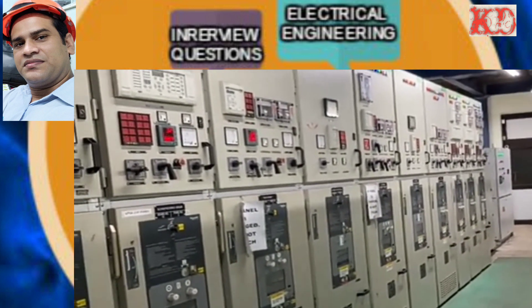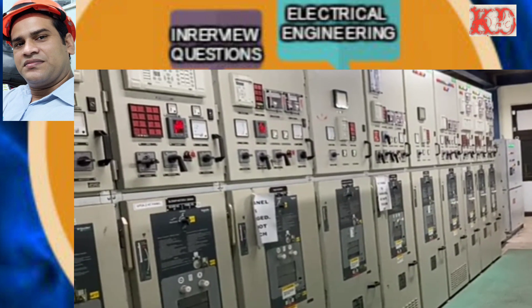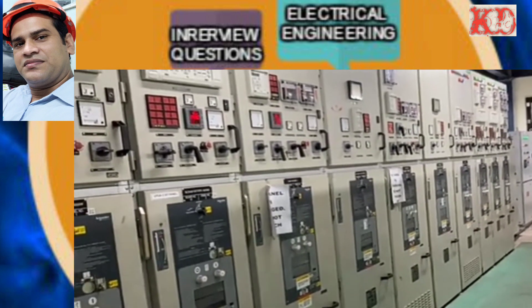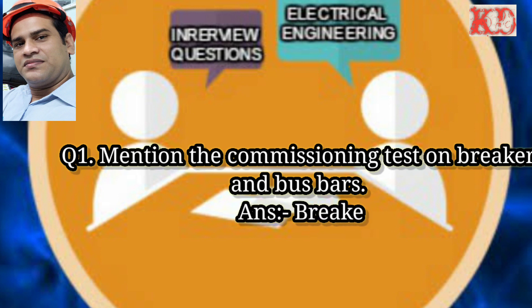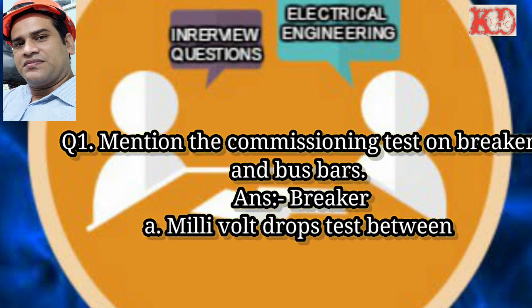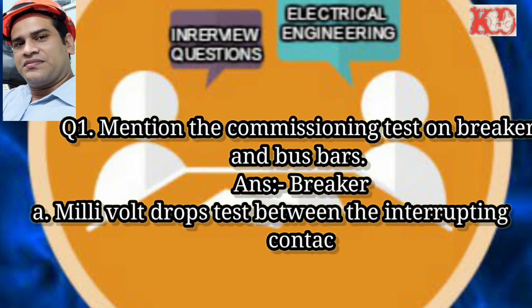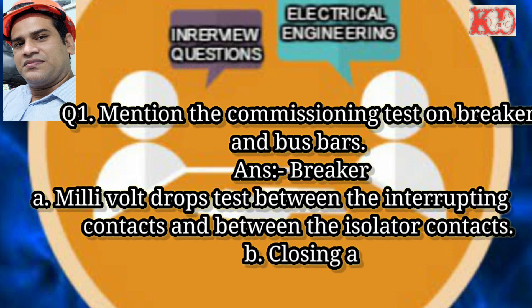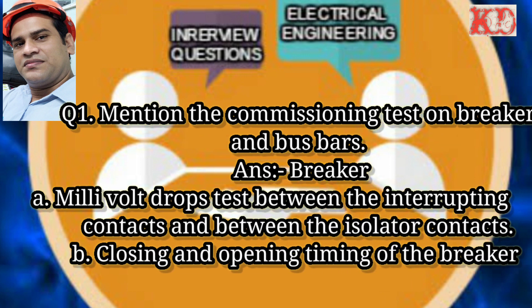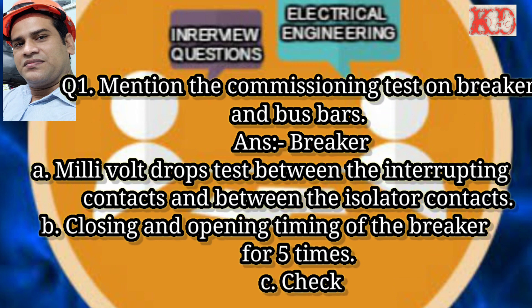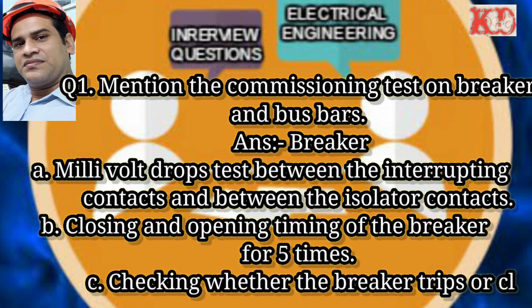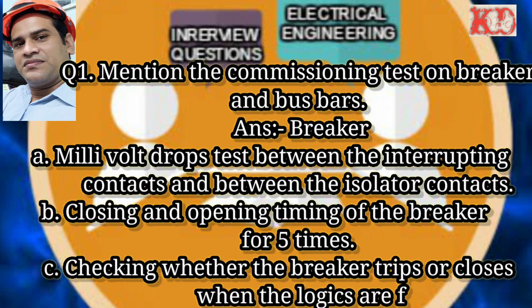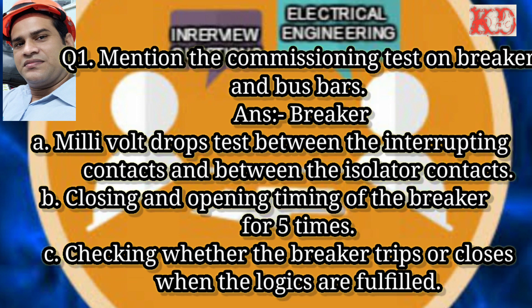Question number one: mention the commissioning tests on breaker and bus bars. Answer — for breaker commissioning, keep in mind: first, millivolt drop test between the interrupting contacts and between the isolator contacts; second, closing and opening timing of the breaker for five times; third, checking whether the breaker trips or closes when the logics are fulfilled.